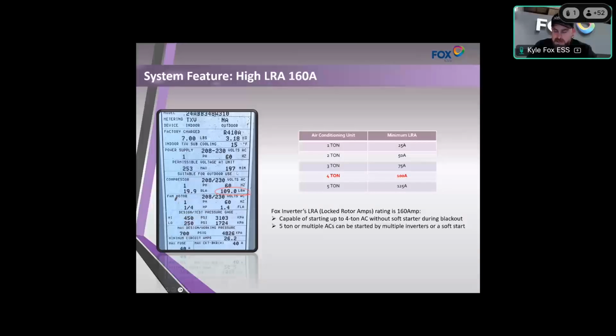So it's a very important feature to pay attention to, because with any battery system, if you overload the start capacity, it will not start. Then you have to go back out there, turn off all the breakers in the panel, and turn them on one by one to see which one is taking up the most load. So it's really important to pay attention to this when it comes to batteries and whole home backup.